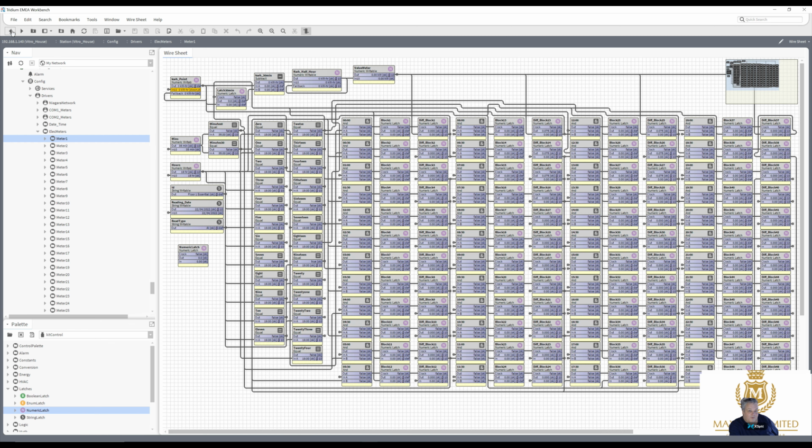What that does is, if your station is rebooted, power goes off and it's restarted again, it clears the data and puts it back to a zero value. Well, we don't want that. We want to keep that data in the out block until it's re-triggered again, which is going to be the following day at whatever time it is.